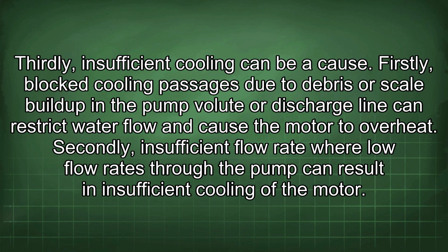Firstly, blocked cooling passages due to debris or scale buildup in the pump volute or discharge line can restrict water flow and cause the motor to overheat. Secondly, insufficient flow rate, or low flow rates through the pump, can result in insufficient cooling of the motor.